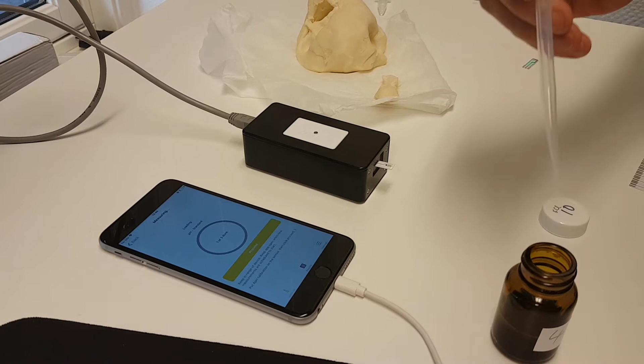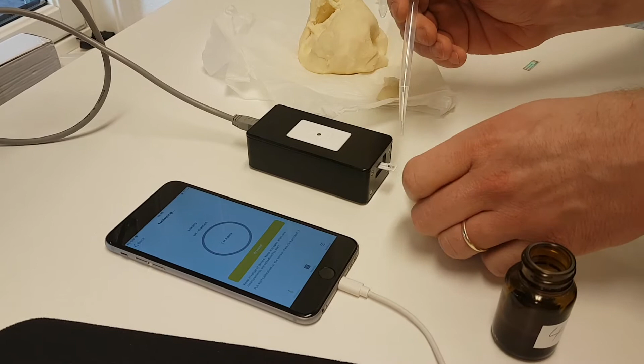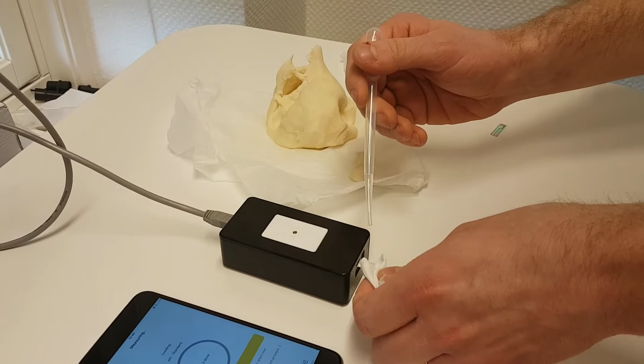Alright, so now we've finished our first 60-second calibration cycle. Now we're just going to wick this gently off the sensor, just using a piece of paper, and we touch the drop. Just make sure that we get most of this out of the way. And if we don't get all of it in one go, we can flush it with our next calibration solution, which is pH 4. So we can just introduce the sample and then just wick it away, and that way you make sure that you have only pH 4 on there for this step.